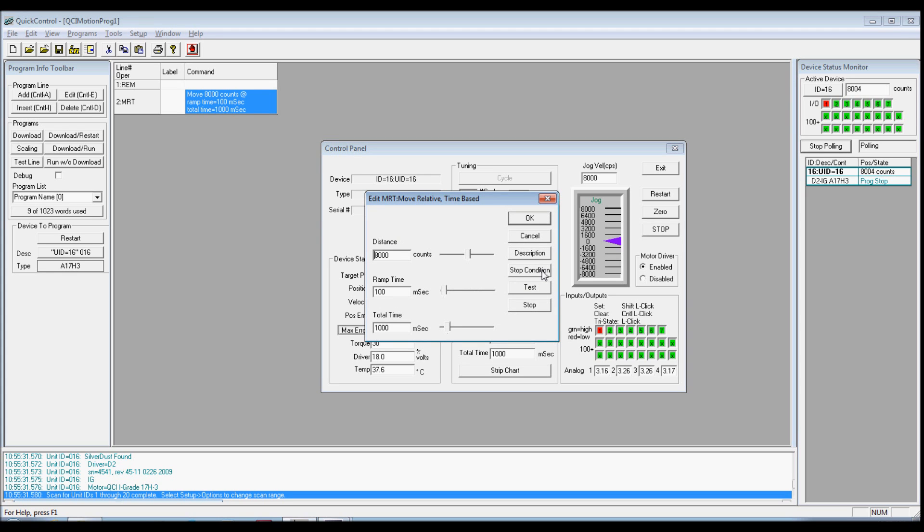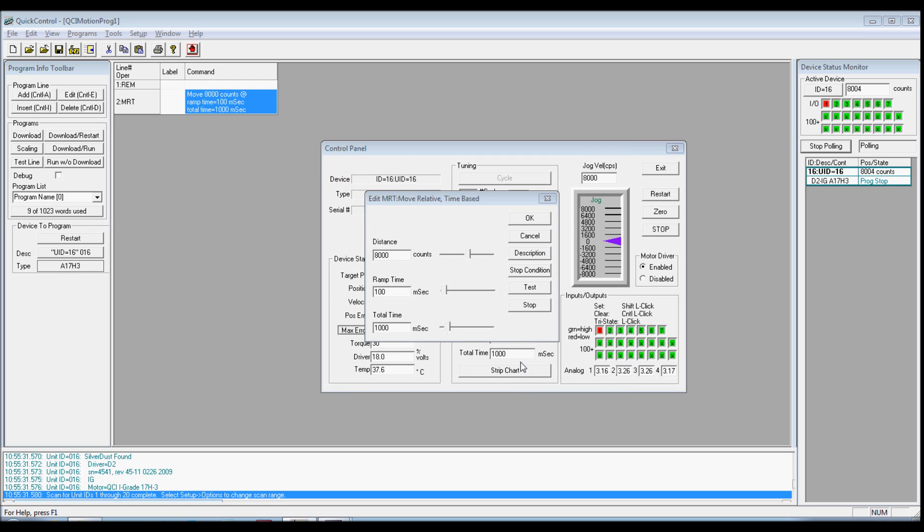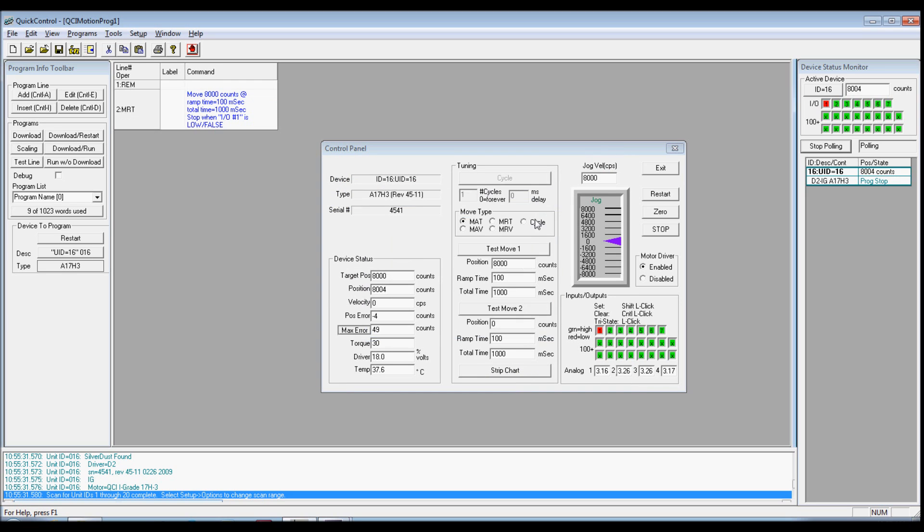Double-click on the existing MRT command in your program. Press the Stop Condition button on the edit box when it pops up. Select the Standard tab. Select the I/O 1 condition and low/false state. This selection will cause your move to stop when I/O 1 is low. Press OK to save and exit the Edit Move dialog box.